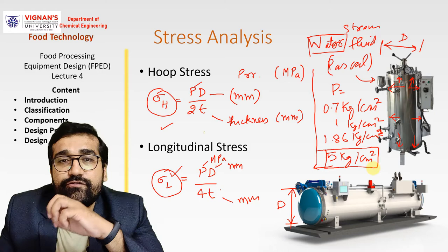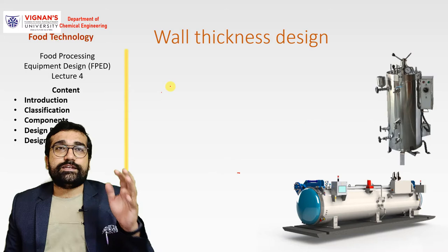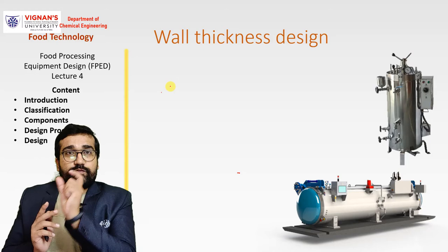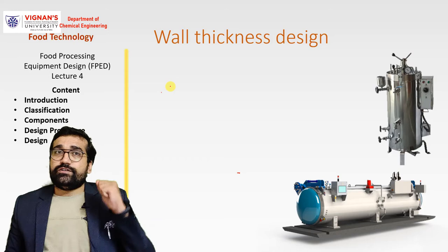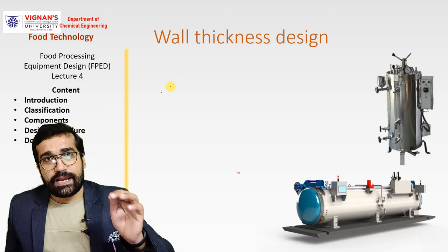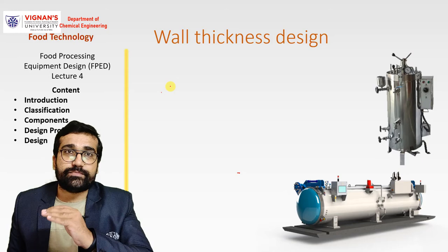So next is wall thickness design, where we design the thickness of the wall. So what is the thickness of the wall? The thickness of the sheet we are using to design the autoclave sterilizer. So how to find that? We find the thickness of the sterilizer by applying the maximum stress acting on the surface, which is hoop stress, which is PD by 2T.